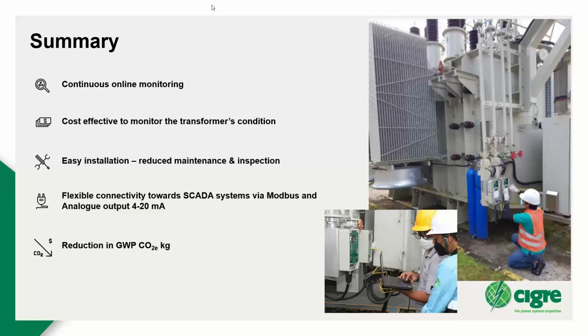I would say, if you try to use percent saturation under laboratory conditions, you need a capacitive sensor. Capacitive sensors, to work properly, must always have a very big flow of oil, which is difficult, and they also need a very big response time. So I'm skeptical that one can use capacitive sensors successfully under laboratory conditions; the results will be quite different. Additionally, you have the problem that you don't have the actual transformer temperature. So, to be honest, I would not recommend using relative saturation for samples taken from a transformer and brought into a laboratory. But of course, this is my opinion and experience.